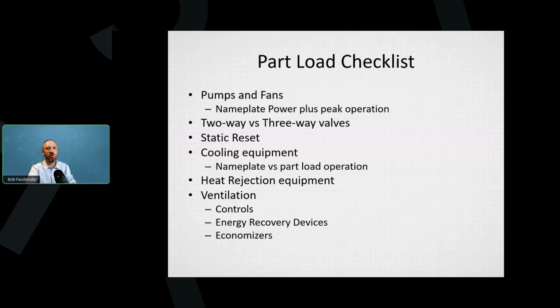A huge impact, not necessarily with modeling, is the ventilation. If the controls are working, the energy recovery devices are working, economizers are working. If someone jammed a screwdriver into the ventilation damper, those are things that you want to know, because that ends up being a huge amount of energy. And if you run some of this wrong, it can also cost you a lot of energy. So you want the controls to balance.